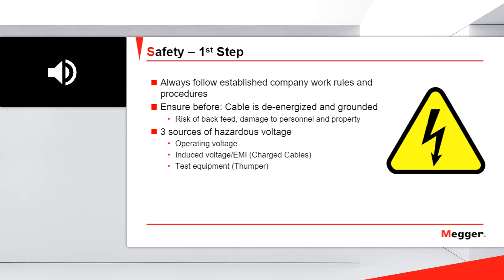Okay, safety. Of course, you always need to follow the established company work rules and procedures, and you should be aware of the three sources of high voltage. The first one is the operating voltage. The second one is the induced voltage. Of course, the faulty cable is de-energized, okay? But it could be that we have energized cables in the same trench or in the same duct. So we need to be aware of those cables because they could induce voltage in my faulted cable, okay?